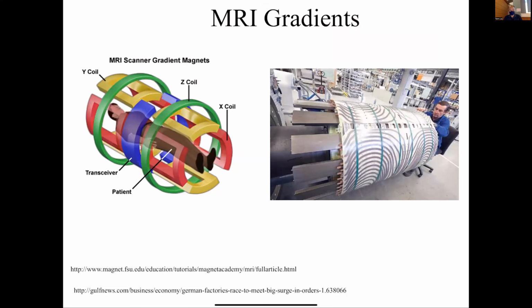Okay, the next coils we're going to talk about are the gradient coils. There will typically be three of these: an X gradient coil, a Y gradient coil, and a Z gradient coil. And this is an example, I think, from the Siemens factory floor. You can see these coils have very interesting patterns, and right now they're all computer designed to optimize their performance.